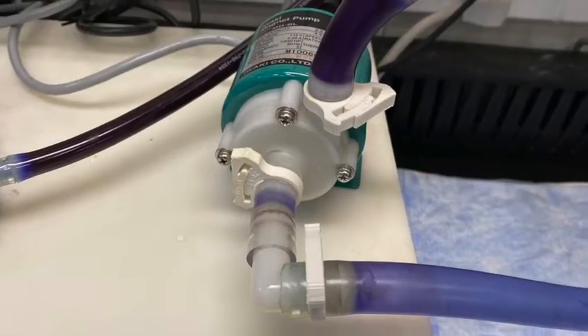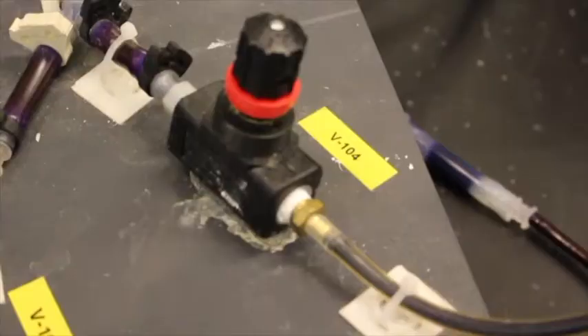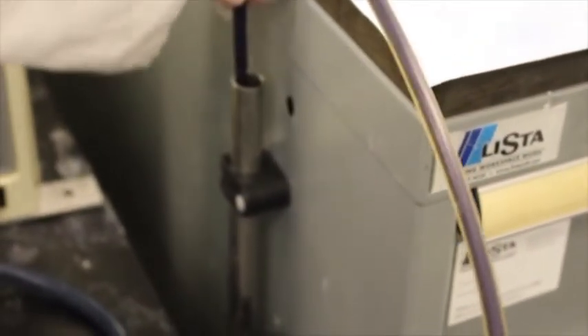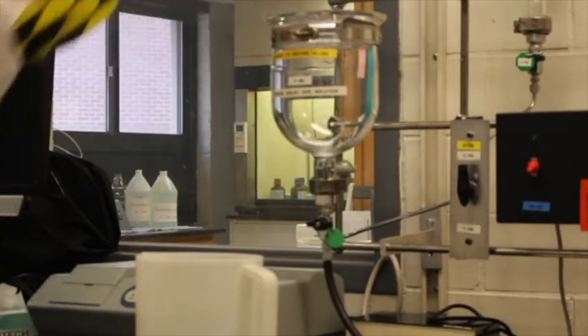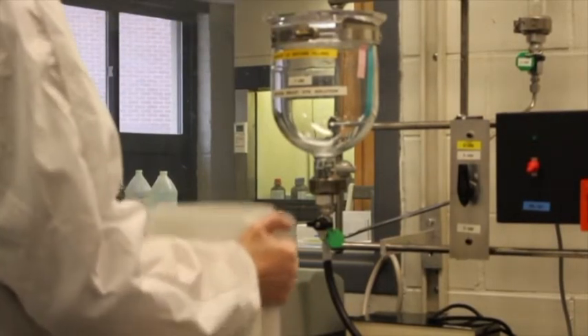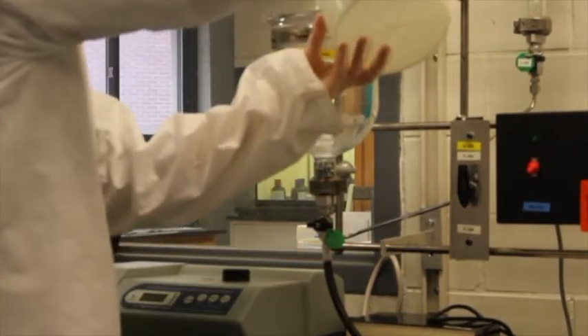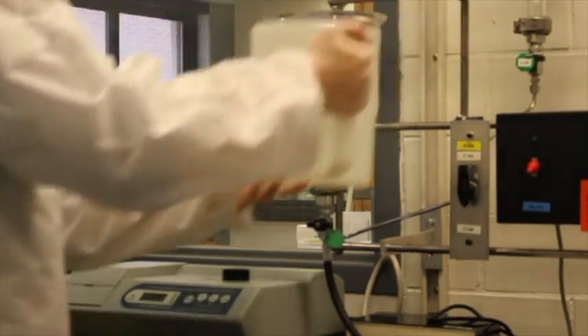Now check to make sure all tubing connections are secure. Ensure that the tube from V104 is placed in the drain. Fill tanks T100 and T101 with water for the calibration by opening the lids of the tank and then closing the lids before beginning the calibrations.